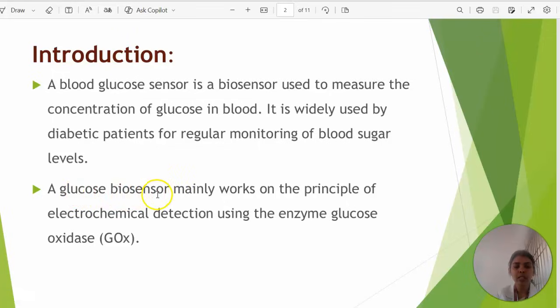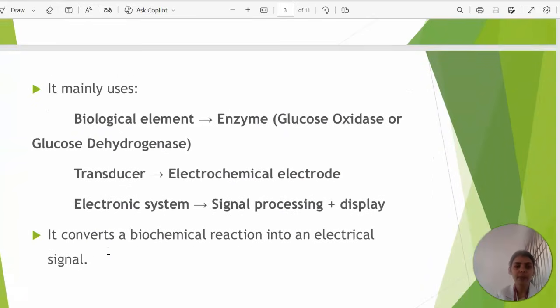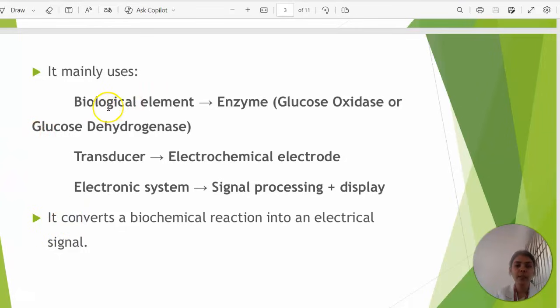A glucose biosensor mainly works on the principle of electrochemical detection using the enzyme glucose oxidase. It mainly uses a biological element, a transducer and an electronic system. The biological element is an enzyme, the transducer is an electrochemical electrode, and the electronic system is a combination of signal processing and display unit. It converts a biochemical reaction into an electrical signal.